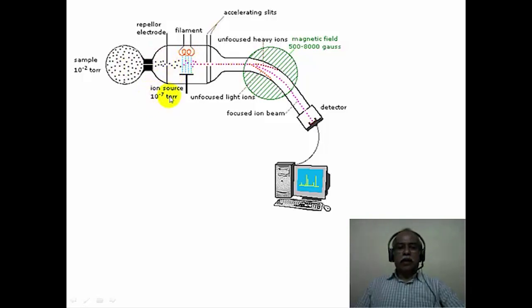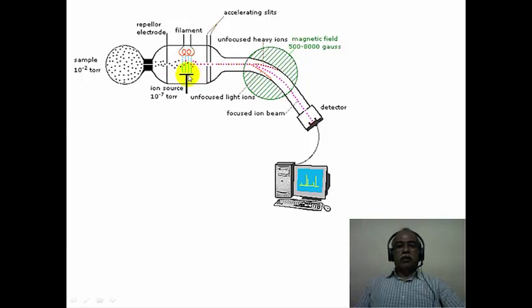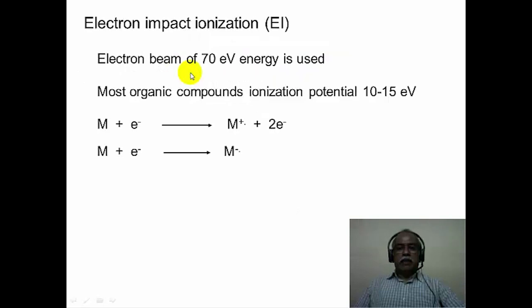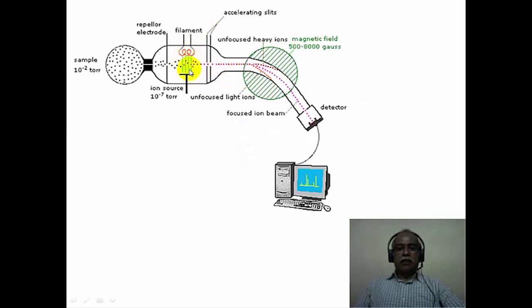The ionization chamber is maintained at a much higher vacuum of 10 to the power minus 7 torr or 10 to the power minus 6 torr, and essentially consists of a cathode ray tube kind of arrangement with two electrodes. One of them is a heated filament which produces high energy electrons that get attracted to the positive electrode. The sample passes through a slit through this electrode and is brought under the stream of high energy electrons, and this is the process by which ionization takes place.